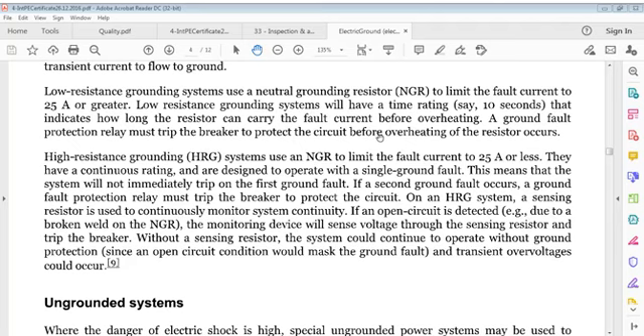Low resistance grounding systems shall have a time rating, say 10 seconds, that indicates how long the resistor can carry fault current before overheating. A ground fault protection relay must trip the breaker to protect the circuit before overheating of the resistor occurs.